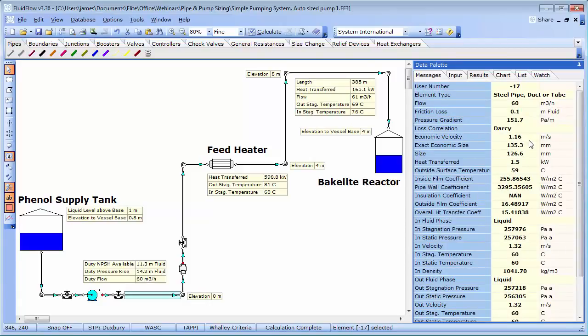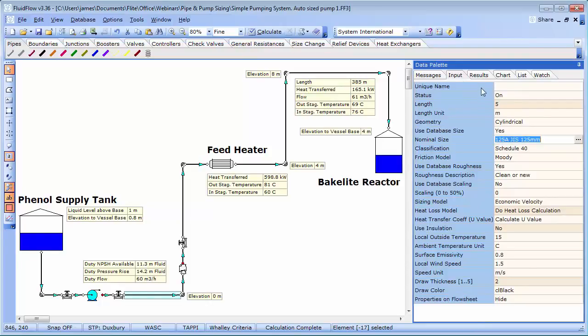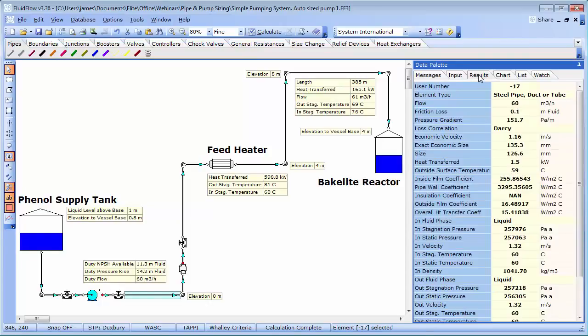Which gives us an exact economic pipe size of 135.3 millimetres. And as a side note, you can determine the economic velocity from our free online calculator on our website or using fluid flow software. Using the near standard pipe size to 135.3 millimetres for steel pipework means we either choose a 125 or 150 millimetre pipe. And we can see here using a 125 millimetre pipe gives us a velocity of 1.32 metres per second.